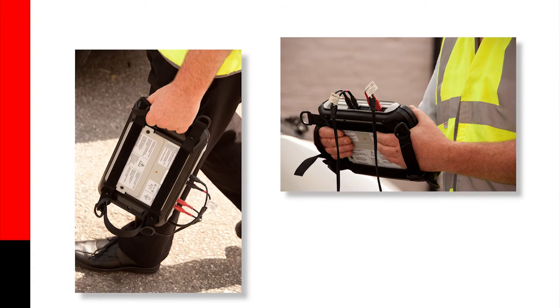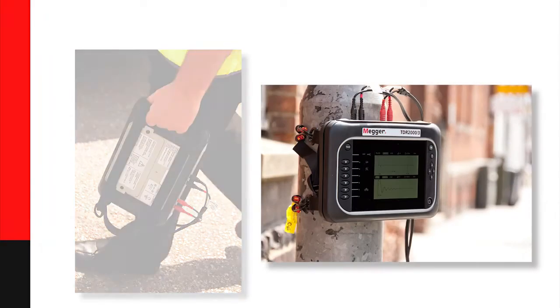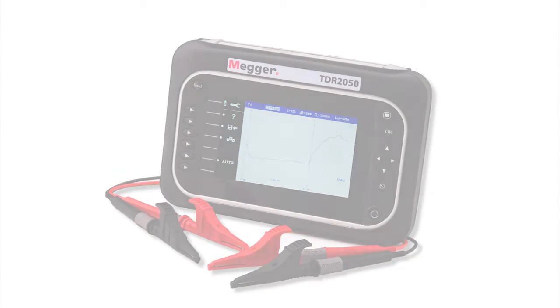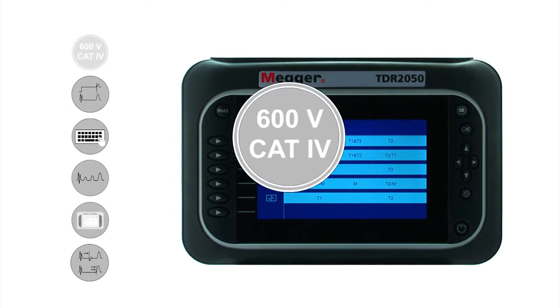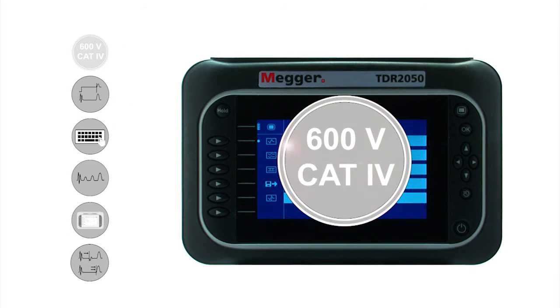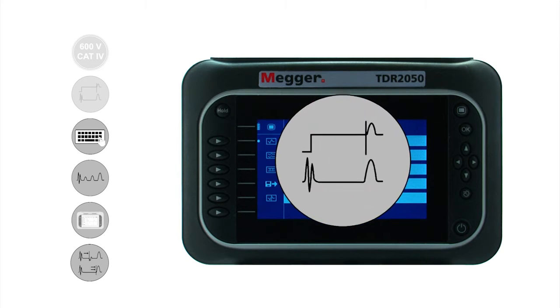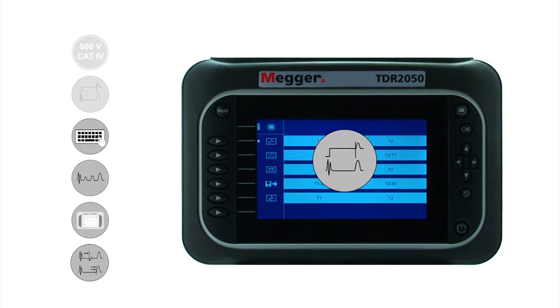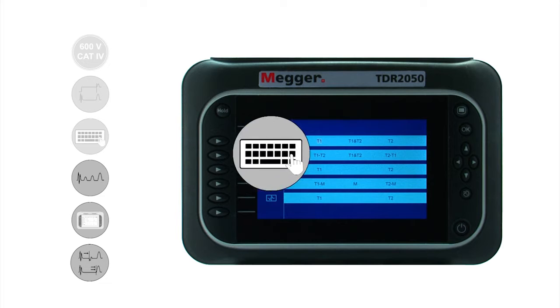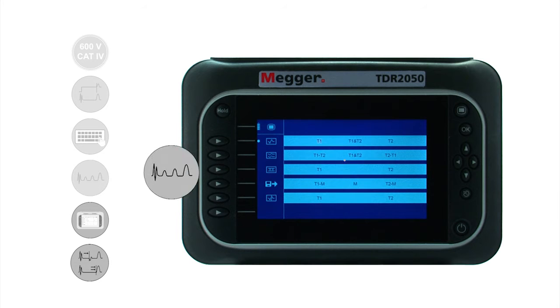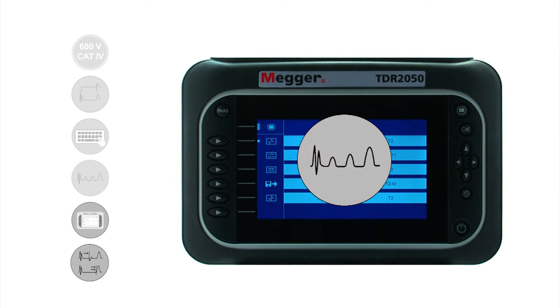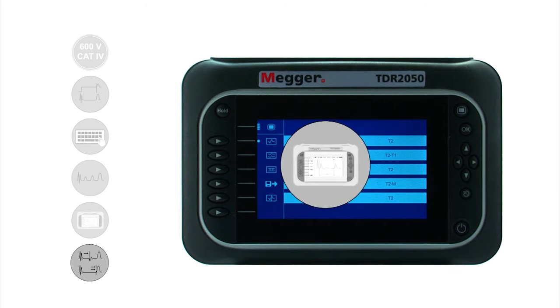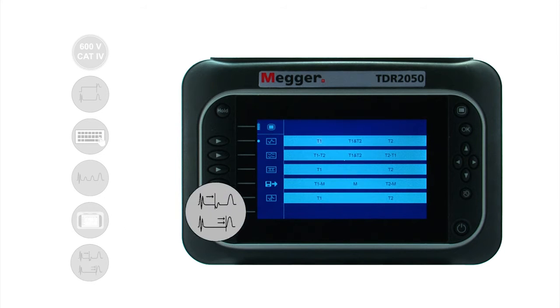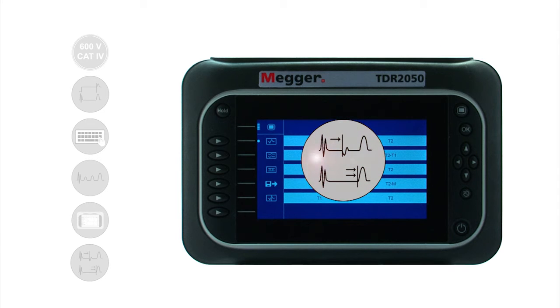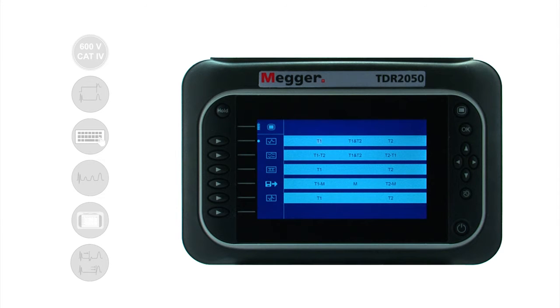The Megger TDR2050 is a dual-channel, dual-trace TDR with a high-resolution colour screen for locating faults on paired metallic cables. The instrument has Cat4 600V input protection built in, step and pulse TDR options to see both near and far-end faults, trace tagging for recording circuit ID, distance-dependent gain to minimise signal attenuation, a trace hold feature for instant trace comparison, auto-find and find-end functions allowing speedy fault identification.